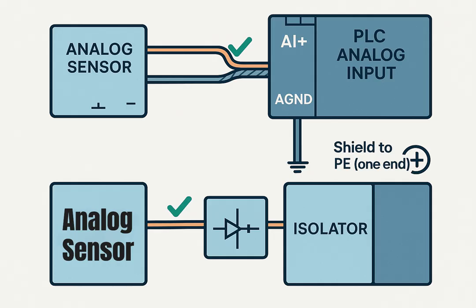Many people are taught the rule: all grounds should meet at a single point to avoid loops. The idea is correct, but if you choose the wrong single point, you end up collecting all noise exactly where your signal reference is. In the wrong schematic, sensor GND goes to the PE bar. The PE bar already carries various leakage currents and noise. Your small analog signal, only a few volts, shares the same path with fault currents and high-frequency interference. The problem: PE is not designed to be a precision signal reference. The potential of the PE bar can move up and down, especially with power electronics. Every time the VFD switches or a contactor toggles, you may see a glitch in the analog reading. So, the concept of one common ground point is correct, but that point must be the signal ground, analog GND, not the PE bar.